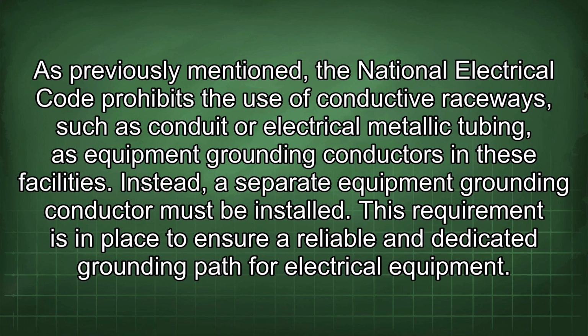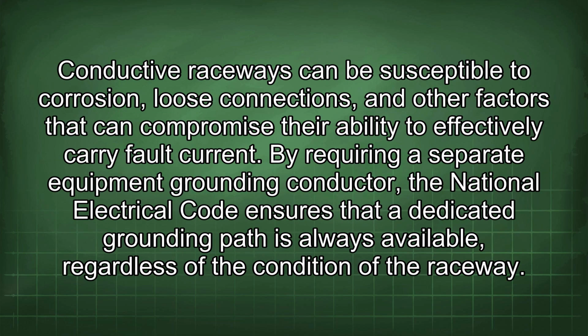As previously mentioned, the National Electrical Code prohibits the use of conductive raceways, such as conduit or electrical metallic tubing, as equipment grounding conductors in these facilities. Instead, a separate equipment grounding conductor must be installed. This requirement is in place to ensure a reliable and dedicated grounding path for electrical equipment. Conductive raceways can be susceptible to corrosion, loose connections, and other factors that can compromise their ability to effectively carry fault current. By requiring a separate equipment grounding conductor, the National Electrical Code ensures that a dedicated grounding path is always available regardless of the condition of the raceway.